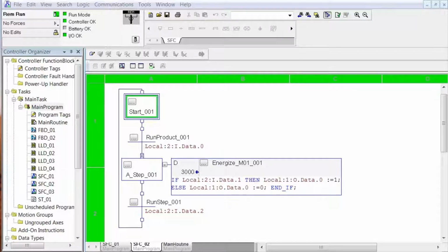Toggle input 0 and then begin toggling input 1 repeatedly for at least 4 seconds. It has to be for longer than the preset on that time delayed qualifier. So we push input 0, then we start pushing input 1 repeatedly. What happened in detail? We went into step 1, we started pushing the button, nothing happened. And at the end of 3 seconds, the output 0 started flashing on and off as we pressed and released input 1. Toggle input 2.